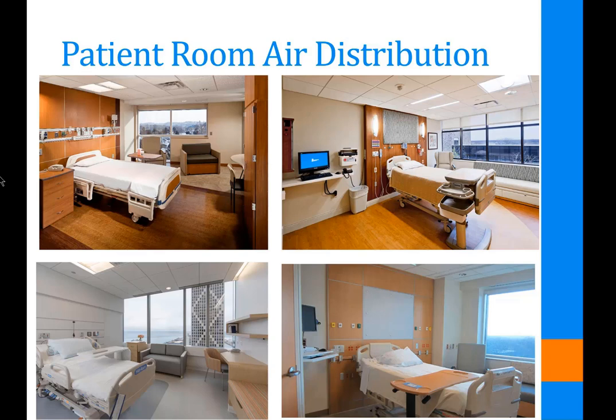An auto changeover diffuser puts 100% of airflow either horizontal across the ceiling for cooling or vertically down the window for heating, giving the same benefit as a well-mixed system in either mode. In cooling, the 100% horizontal throw mixes the room well and reaches set point faster. In heating mode, the vertical throw rolls the room from the bottom, reaching set point 30% more quickly, meaning the patient is comfortable sooner, and you decrease heating requirements for the space.